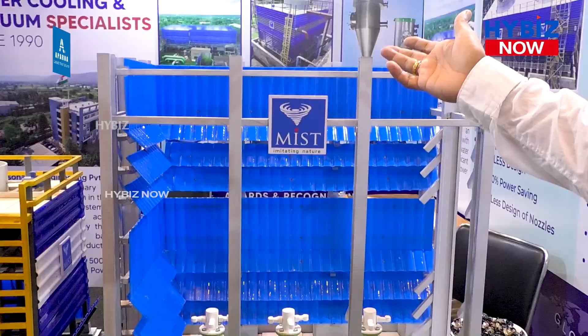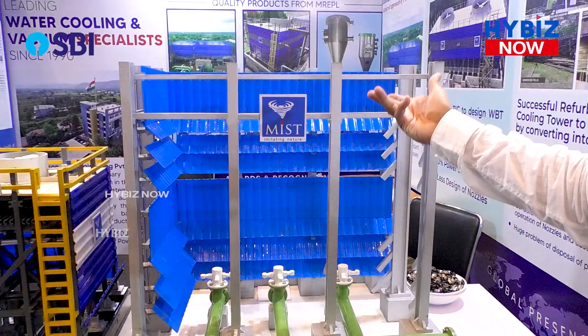The nozzles are placed on the ground level, which spray water upwards. So they go at a height of around 5 to 5.5 meters. The cover sheeting height is 11 meters. The travel time for water is double, that is, they go up to 5 meters and come back down. So they eventually remain in air for 10 meters, more than 10 to 12 seconds, and the heat transfer happens.